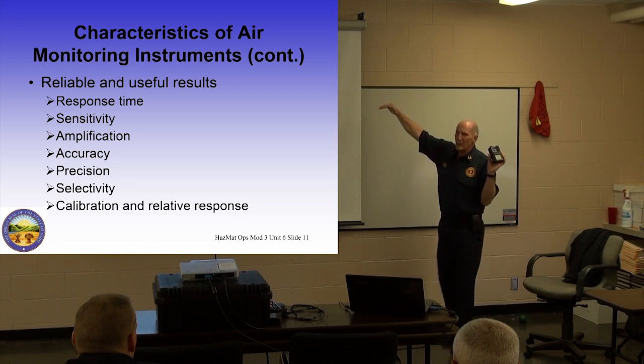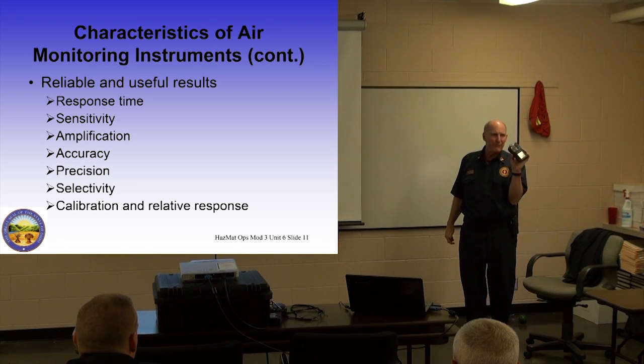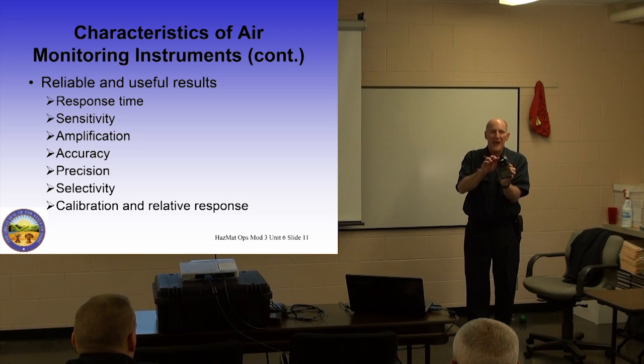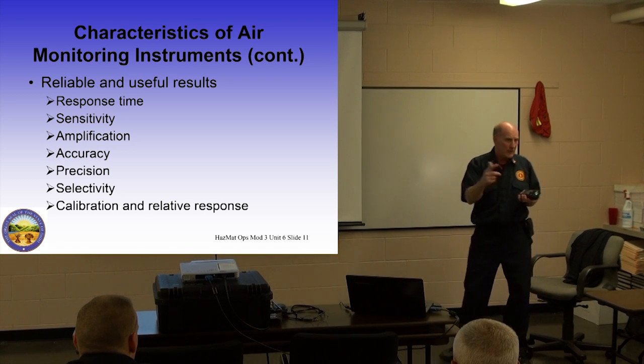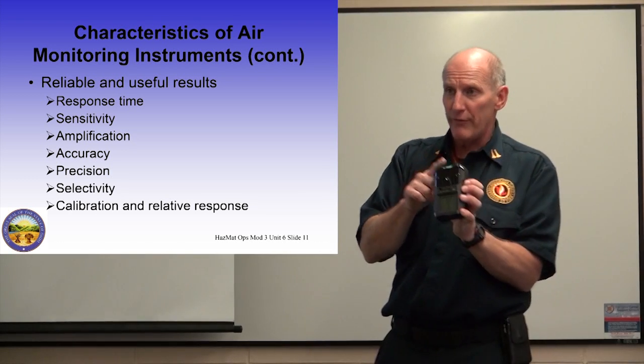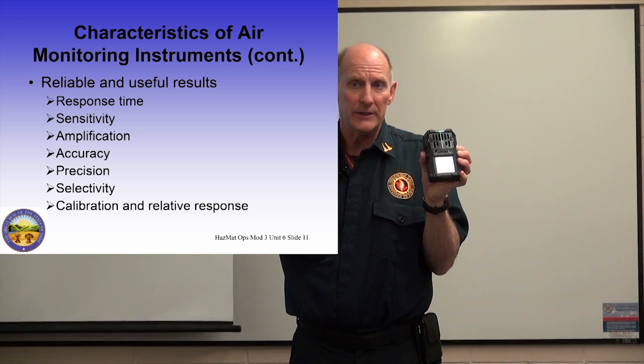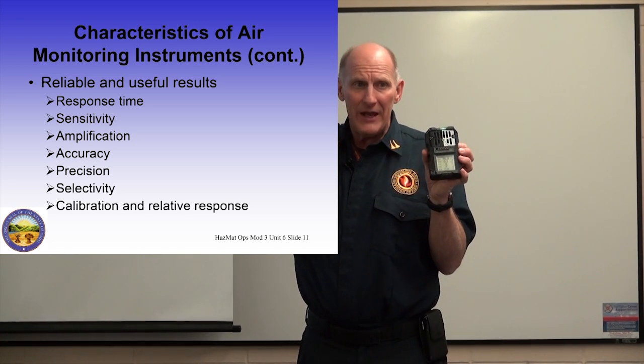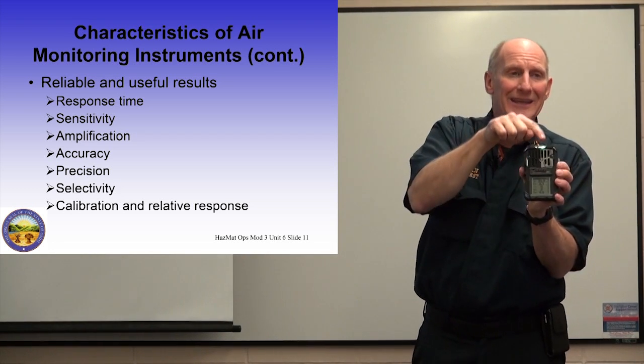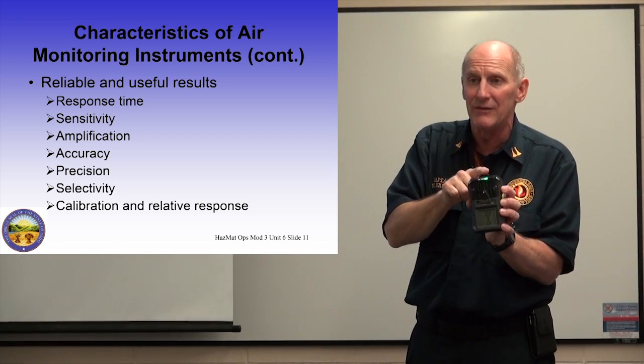The atmosphere isn't bad here. The atmosphere is bad 3 seconds ago. And now you may go from a relatively not too dangerous atmosphere into a deadly atmosphere by continuing 3 or 4 steps. So, response time. How long does it take for it to respond? The rescues have these units with a pump attached. That pump will increase the amount of time it takes for it to respond. So if I have 20 foot of tubing on this, I have to realize that it's going to take even longer for that tubing to get into this and for the instrument to actually give a reading.